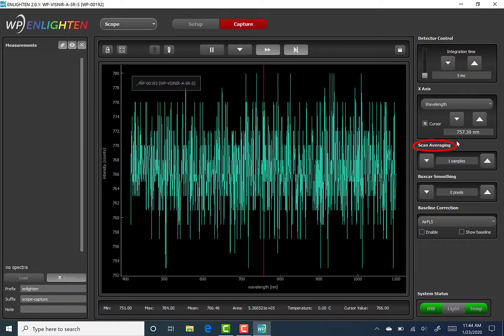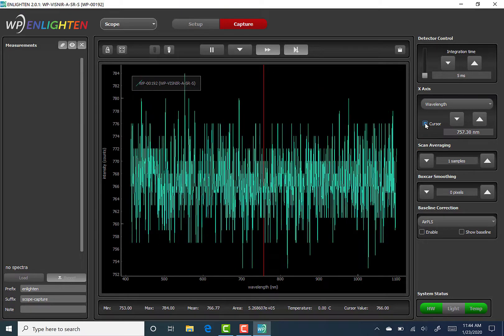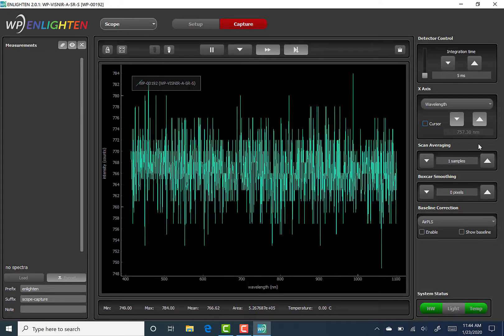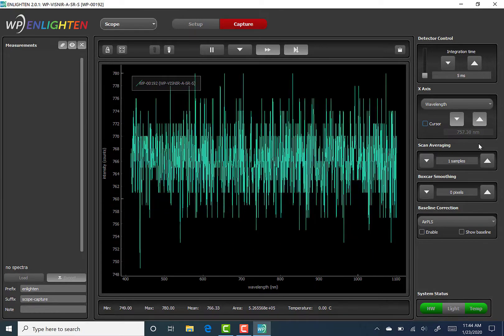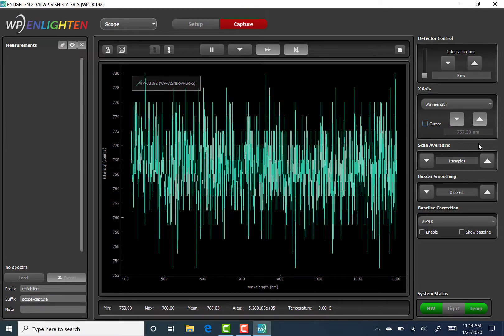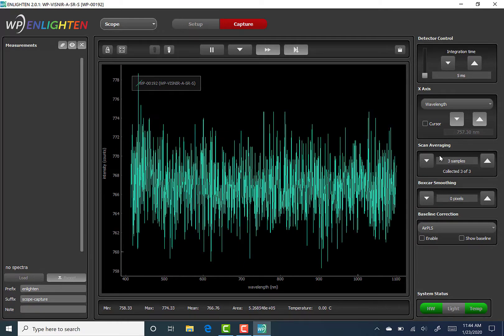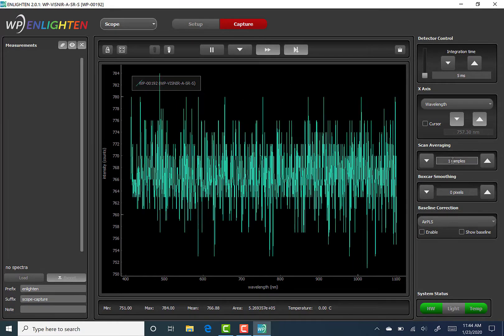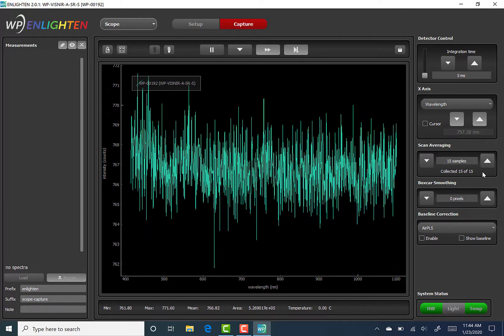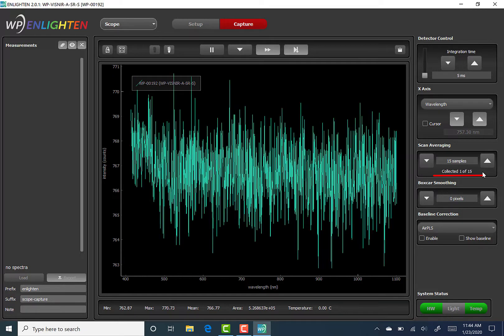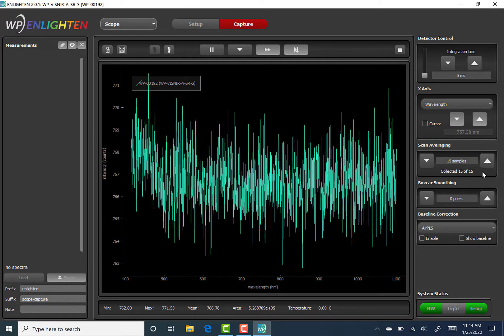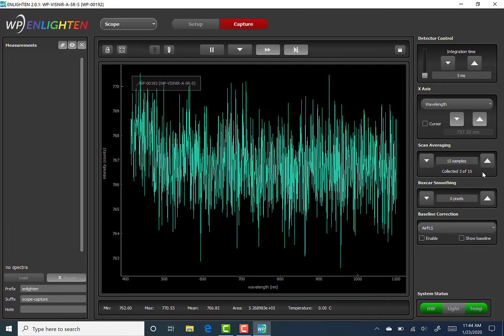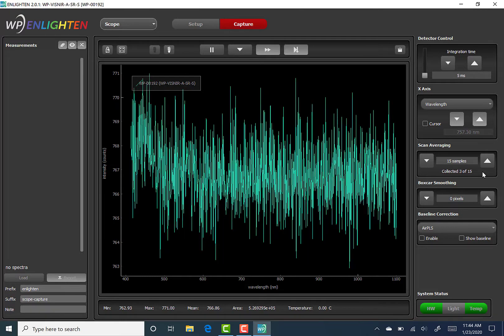Next, we have scan averaging. Scan averaging is one of the most simple ways to improve the signal-to-noise ratio by averaging over time using multiple scans or measurements. To enable this feature, the user can set the number of scans to be averaged by either using the up and down arrows or editing the numeric field shown, like this. When scan averaging is enabled, a secondary text line appears on the control widget stating that the software is collecting X of Y samples. This is so the user can keep track of the measurements in progress. If any changes are done to scan averaging, this will reset the collecting counter to zero.